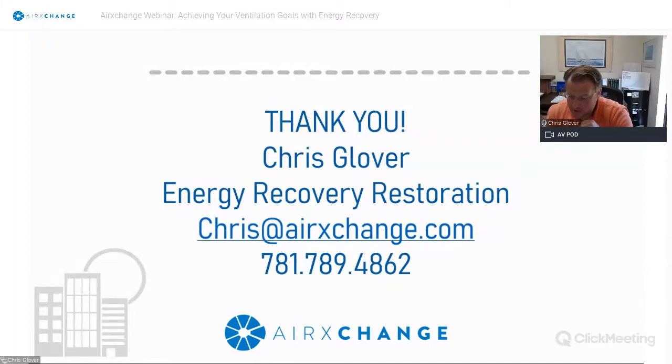Is there any way to provide UV protection and disinfection in the ERU? We got asked this at the beginning of the pandemic period. I don't really see any benefit of having UV in the component compartment for an energy recovery device, because there is no standing water. And usually that air is being delivered downstream to what is being recirculated into the space. It's either delivered into the space or into a duct system that's going into a recirculated air system. And it's really the recirculated air system that would probably benefit the most from a UV light. So you'd probably want to use it in its typical position, which would be in the coil compartment. But I don't really see any added benefit from adding UV to the energy recovery component device.